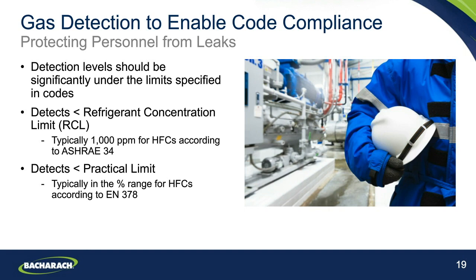But typically, we're talking alarming under 1,000 parts per million for HFCs according to ASHRAE 34. And in EN 378, the practical limit will typically tend to be in the percentage range for HFC as well, although we would typically expect to see people alarming at much lower levels than that.